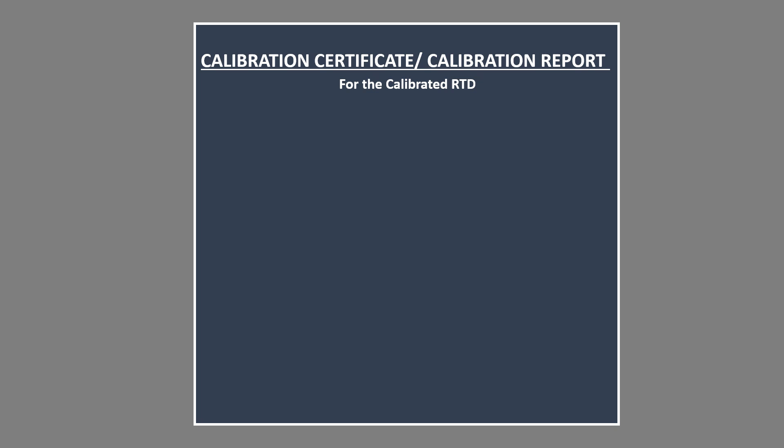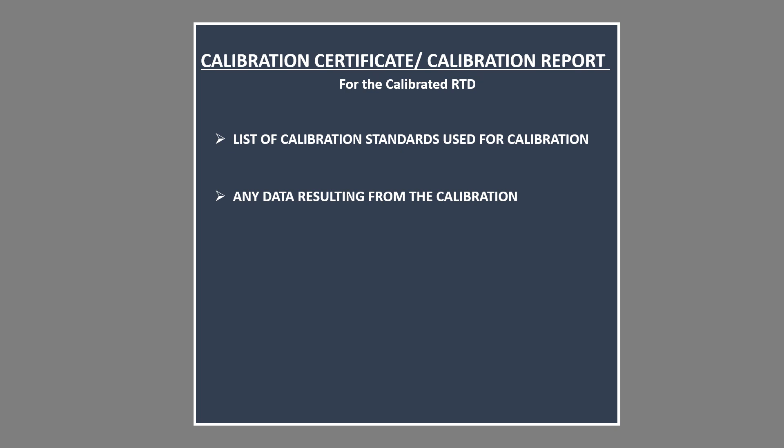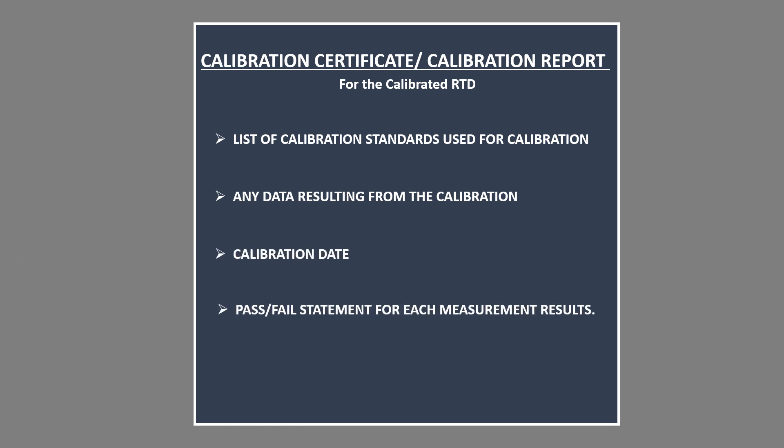A final document called calibration certificate is prepared which contains list of calibration standards used for calibration, any data resulting from the calibration, the calibration date, and possibly pass or fail statement for each measurement result. This is how a typical RTD calibration is done.